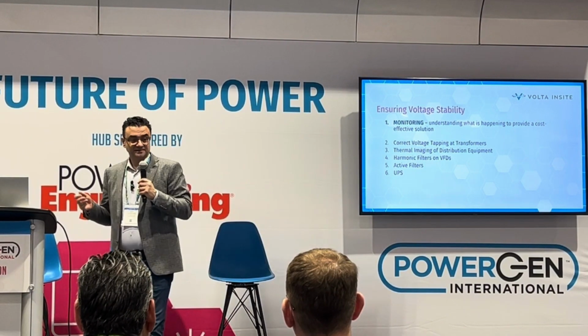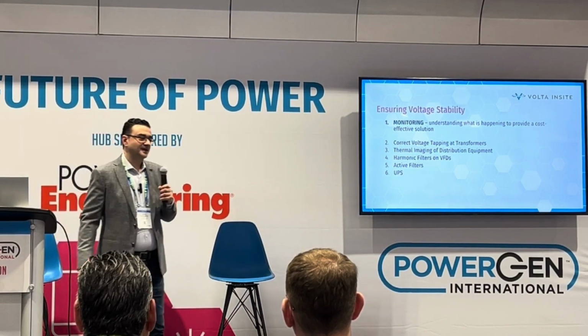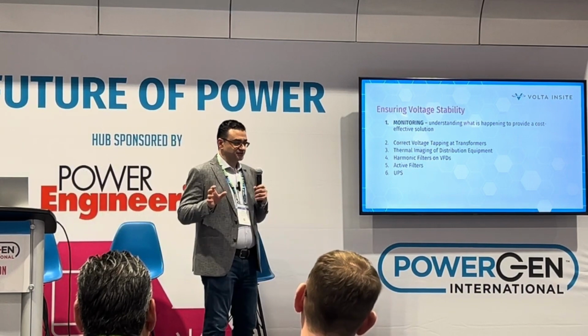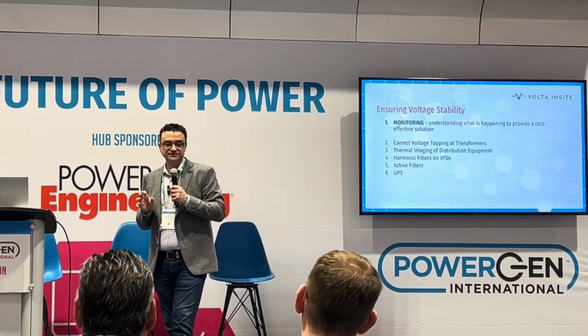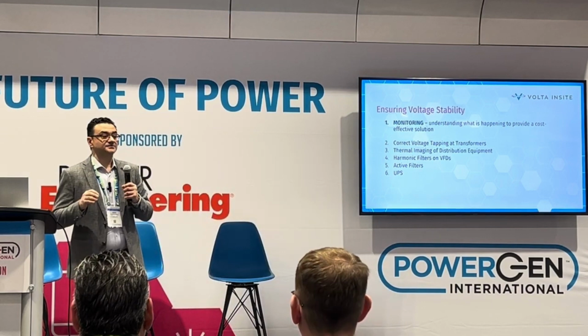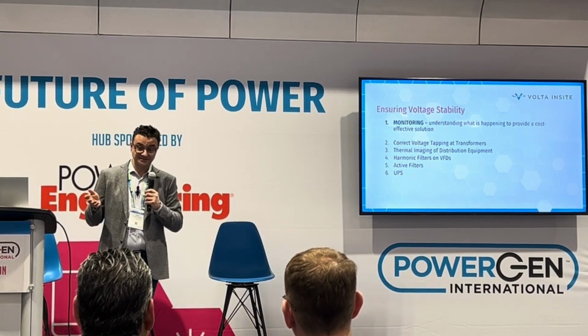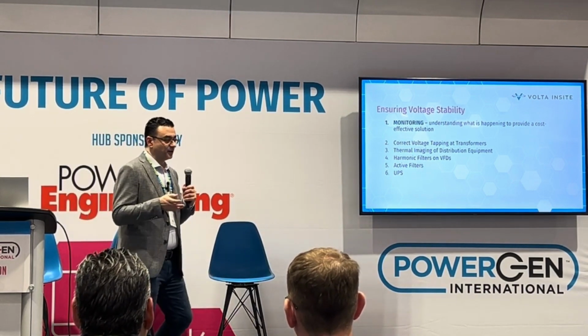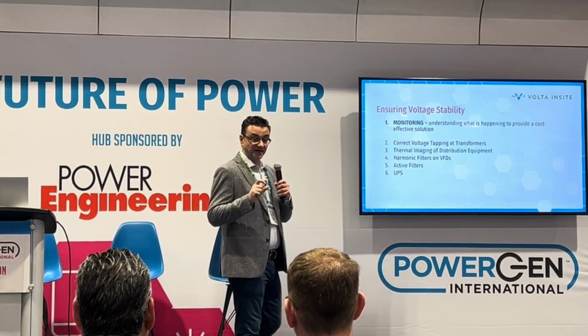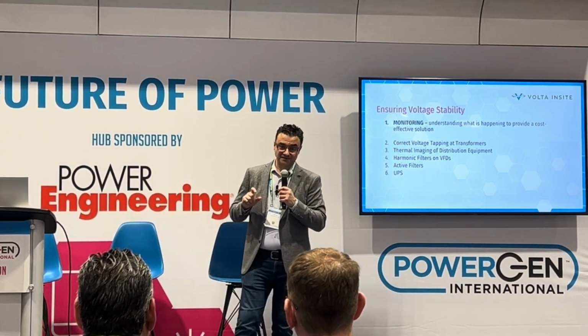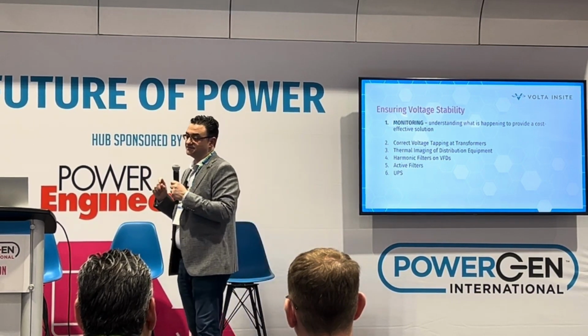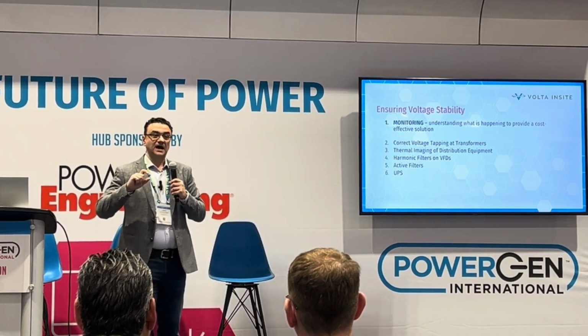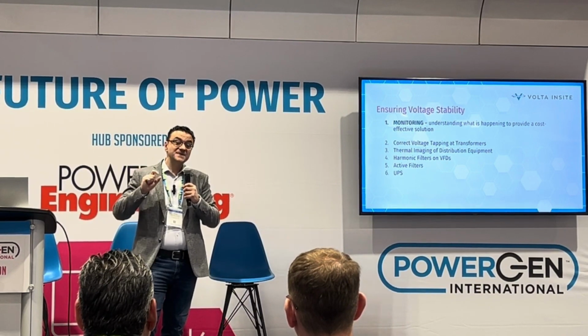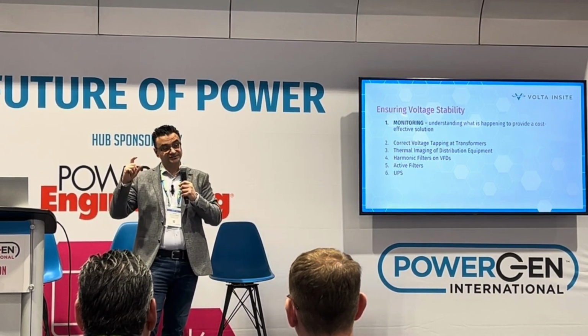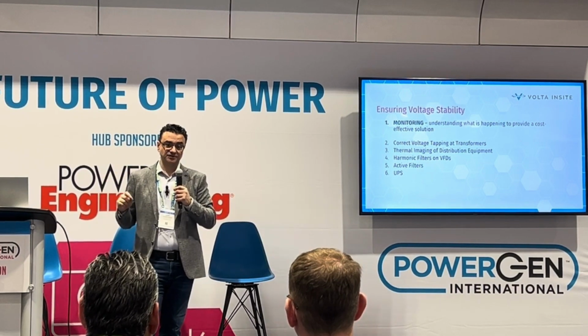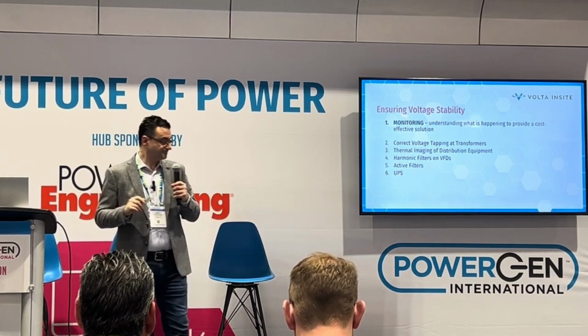okay, that's great, but do we have any data? So we did some captures, and we noticed doing the captures on startup that sure enough, there was a lot of harmonic distortion because of the VFD. However, if you sat down and did some simple calculations, especially under startup, you would notice that the amount of harmonics on that startup with a VFD were minimal in comparison to what the generator could produce. So it shouldn't be a problem theoretically.